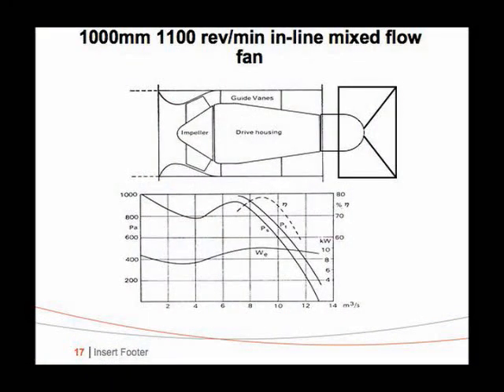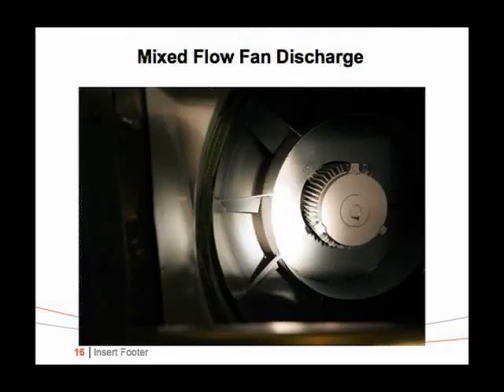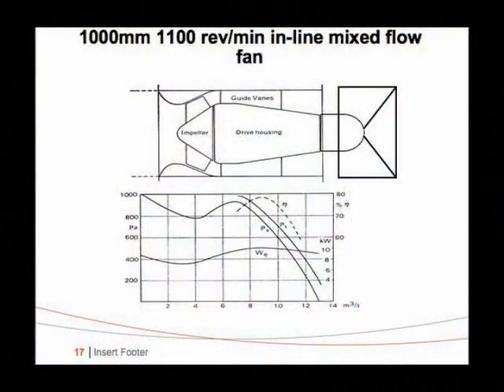Behind that, you have butterfly dampers, normal butterfly, parallel bladed dampers. So that's also losing pressure because your dampers are only seeing air velocity from the annulus at very high discharge speed, so very high noise, and you can hear the dampers rattling. So if you select a high efficiency mixed flow fan, almost 75% peak, 76% peak efficiency, how do you handle the discharge?